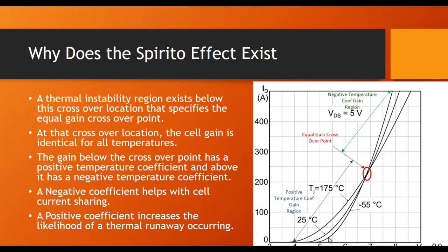Now this is considered a positive temperature coefficient relationship. Above the crossover point the curves switch over where increasing temperature reduces the gain. So this aids in allowing the cells to share current amongst themselves without running into a thermal runaway case.